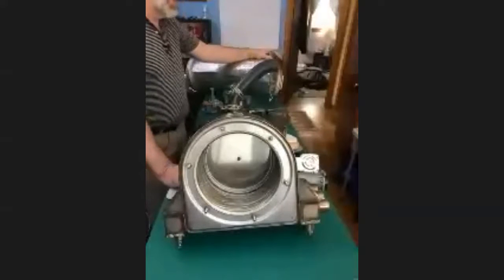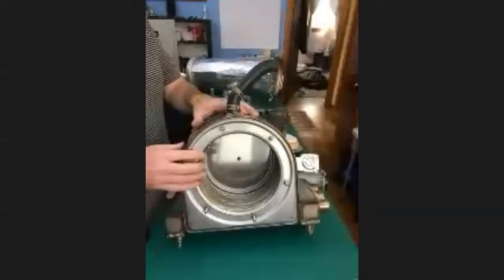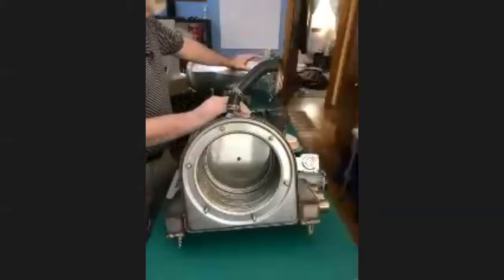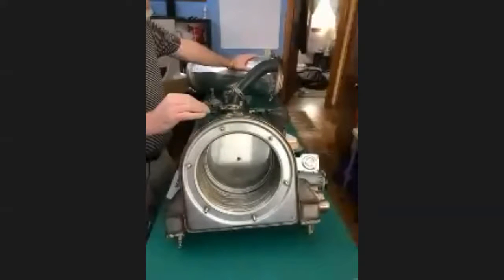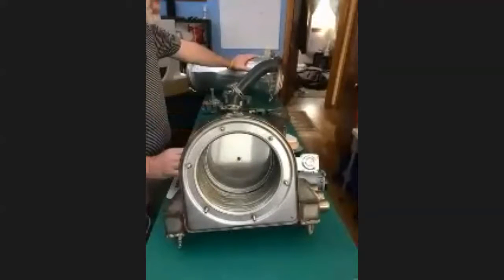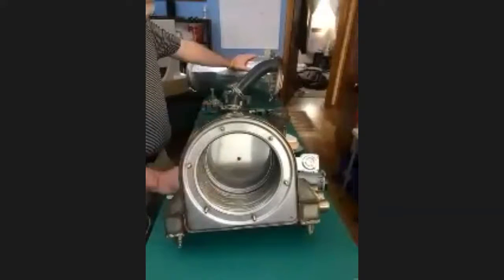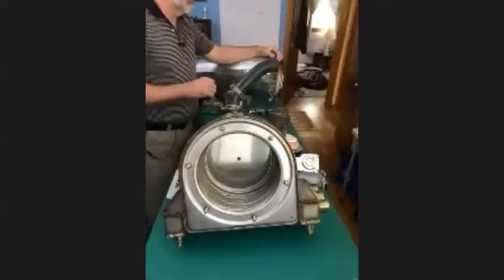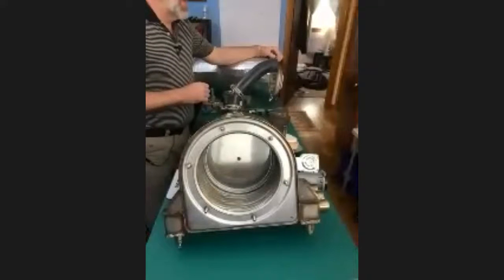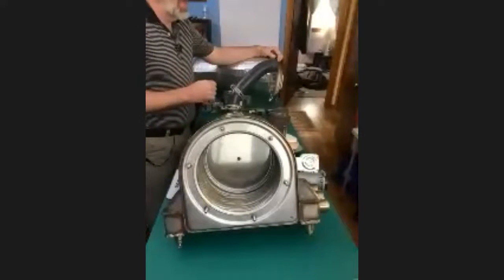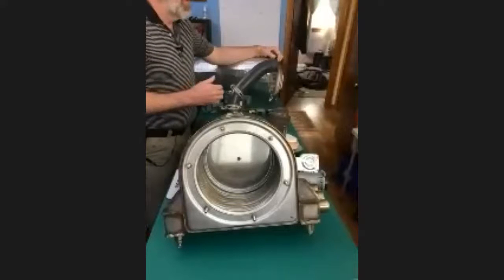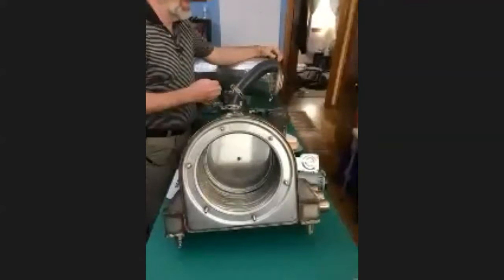Just taking a look right here, this is a water tube style heat exchanger. As you look into it, the tubes on the heat exchanger make for a different sort of experience as far as the cleaning involved. I know the bandwidth is a little bit low, so it's a little bit behind. You have to clean in between those tubes as you go, making sure we don't have any buildup inside the tubes of that heat exchanger. And that one's really important.